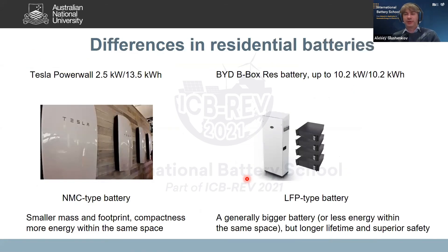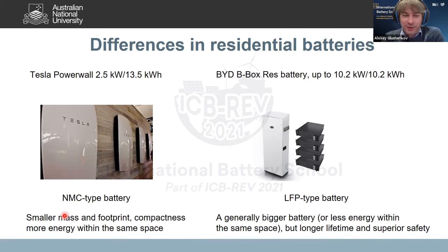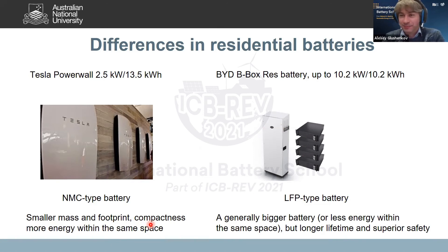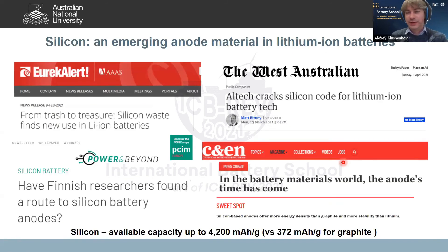In practical terms, consider residential batteries: the Tesla battery uses NMC chemistry and BYD uses LFP chemistry. With NMC, you get a smaller mass and a very compact battery with high energy density — but lifetime may be shorter. With LFP-type batteries, the battery cannot be as compact due to material limitations, but you get superior safety and longer lifetime. Finally, silicon is a strong current trend in industry, with significant challenges but many companies pursuing it with great interest.